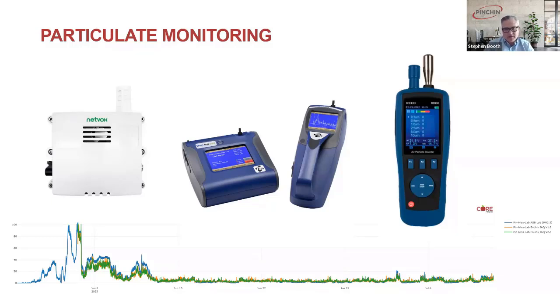A really critical aspect of these handheld devices is all of the standards about when to take action are based on a mass to volume concentration. So micrograms of particulate material per cubic meter or cubic foot of air, mostly cubic meter of air. A lot of the really inexpensive particle counters that you can buy online measure counts per cubic meter. So in this size fraction, PM 2.5, there are 100 pieces of dust in each cubic meter of air. The problem is there's no easy way to bring a comparison from that to the standards.